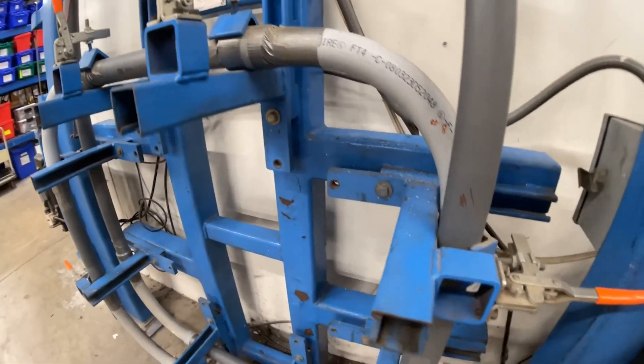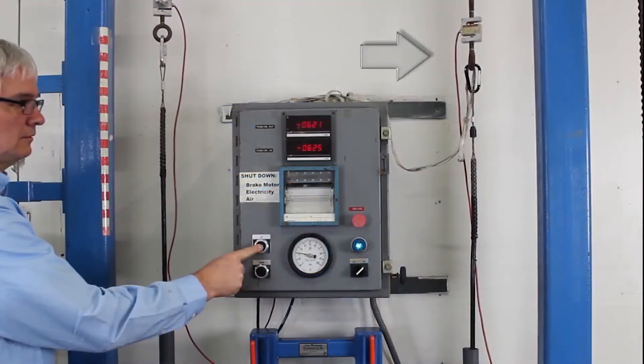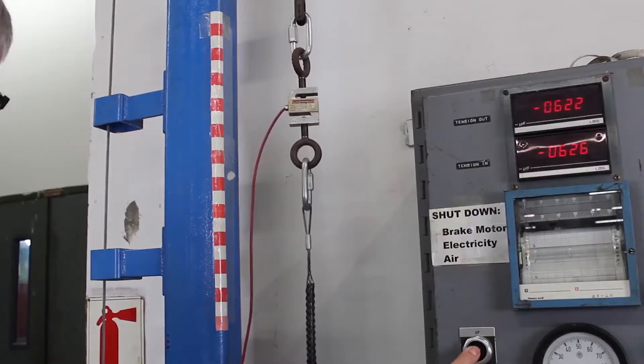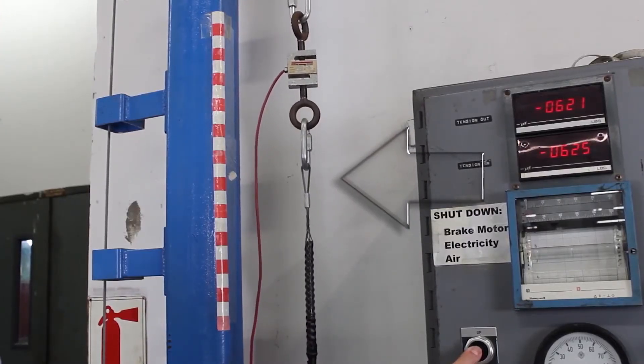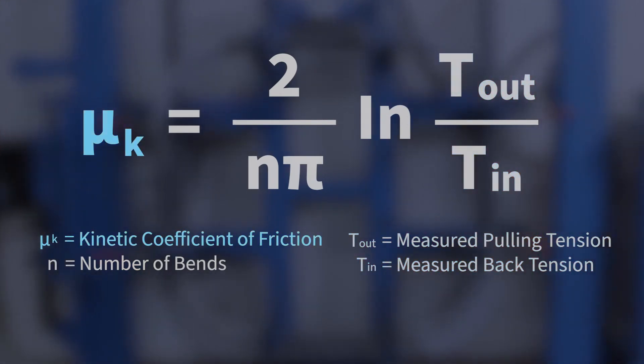Back tension is produced using a pneumatic pressure brake and is measured with a load cell. The pulling winch pulls the cable through multiple bends. Pulling tension is measured with a second load cell. Back tension and pulling tension are used to determine the friction coefficient using a standard formula.